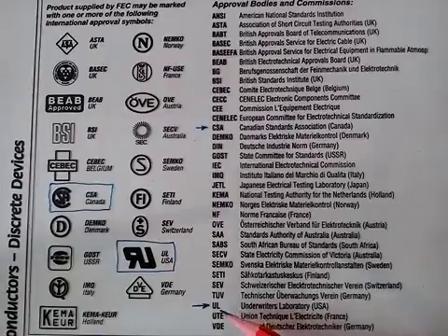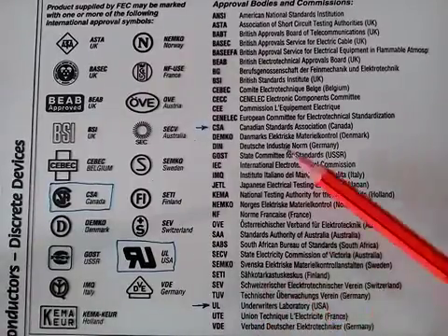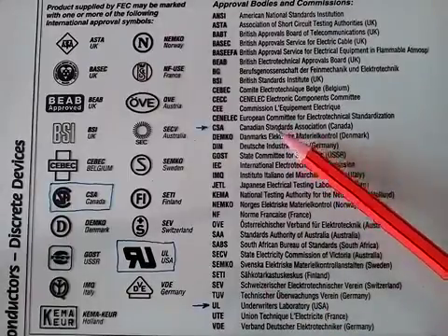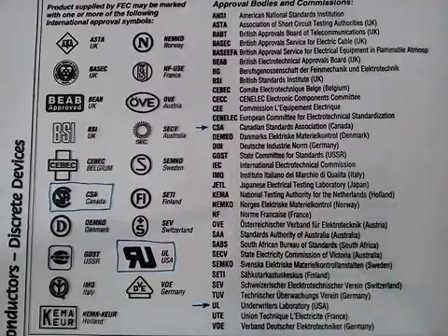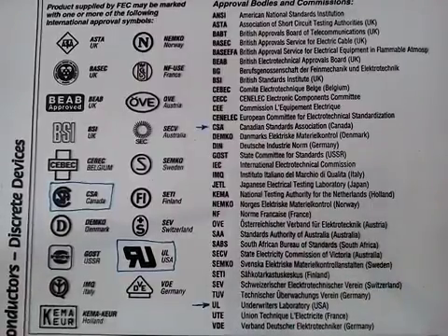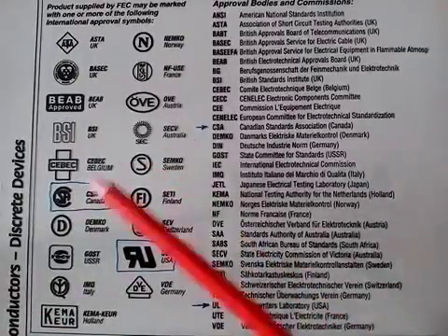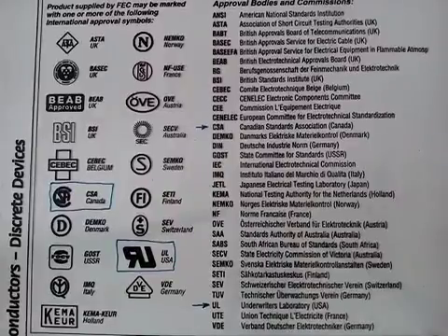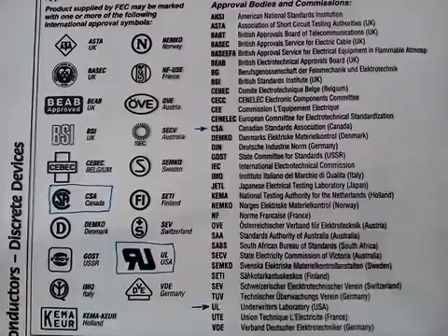Of course, this is the American one under Underwriters Laboratory, and you have the Canadian one. Like we said before in our first lecture, those two labs test fuses differently. Therefore, the values of their fuses are not interchangeable with the rest. They're an international type. Okay.